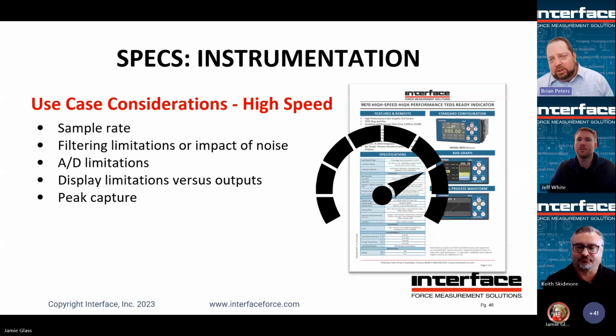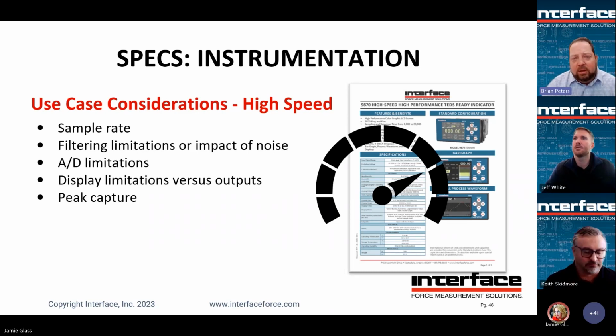And then also the outputs. Many of our signal conditioners, or not many, but some, I should say, are capable of straight pass-throughs. They'll take that analog signal, run it right through the device, and then you have basically a non-filtered pure signal on the outside to take onto your data acquisition or somewhere else. Sometimes there's limitations there in terms of what the pass-through is. Sometimes there's not. So pay close attention to that. And then peak capture. You're going to be able to capture that dynamic event, whether it be either on the display or with your software.